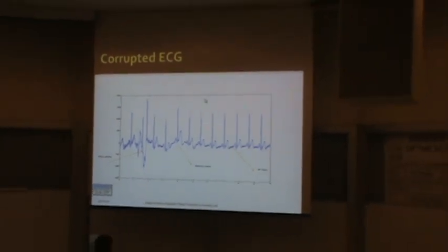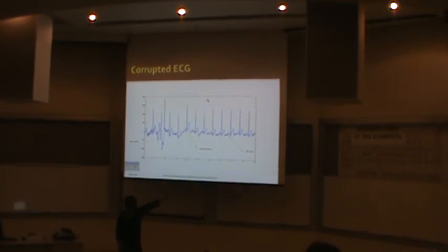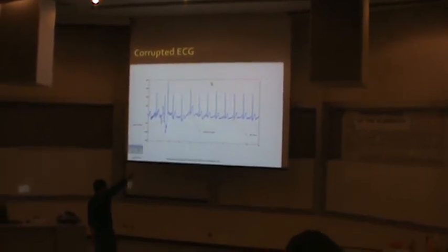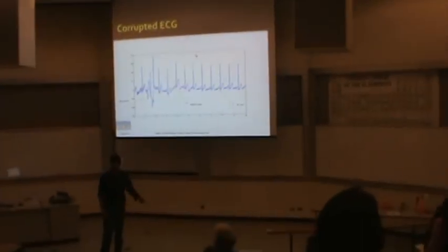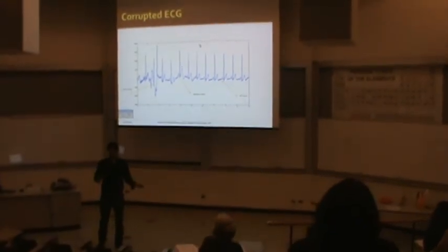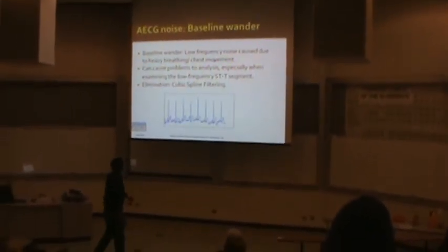High frequency noise. Can you look at the high frequency content there? That's not power line interference, by the way. That is high frequency noise. This is a signal with which the power line interference has been removed. Normally, power line interference can be removed in the hardware itself. You need not go to software. A simple notch filter can be put in the hardware.